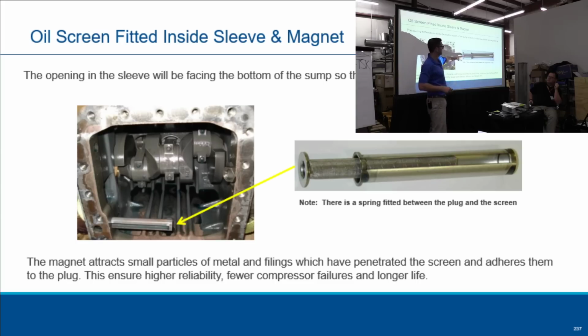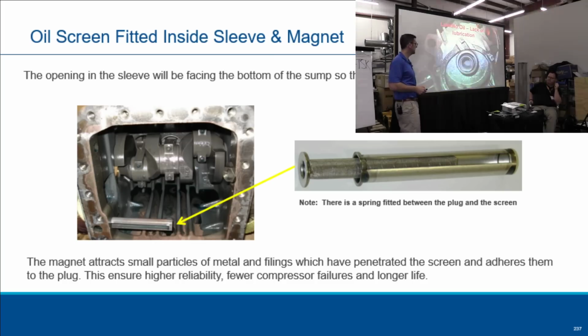What's this here? Does anybody know? Pick up screen. Okay. Should this be pointed down or up, this thing? And this is a big one, and I've talked to lots of contractors about this. Should it be down or up? Up, you say? Down. But you can jam it in and just turn it on and have it pointing up. If it's pointing up, you're not getting all the oil. So if you do start to run on low oil, you're not getting that oil in there. So this should always point down. There's a little tip on there too so that it'll slide right in perfectly.